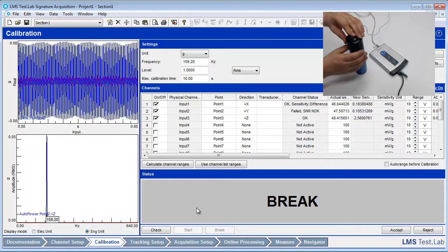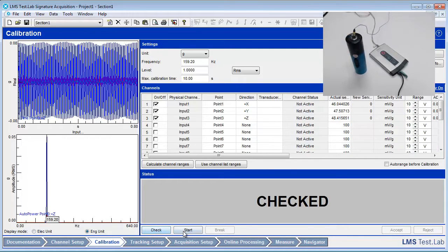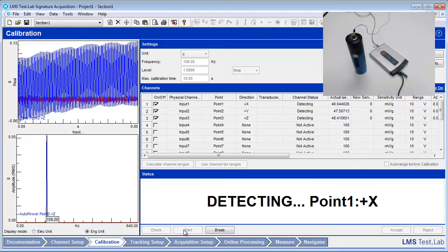LMS TestLab will then calibrate each direction of the triaxial accelerometer separately, one at a time. Let's calibrate again. Press the check button and then the start button. This should calibrate the Z direction only.